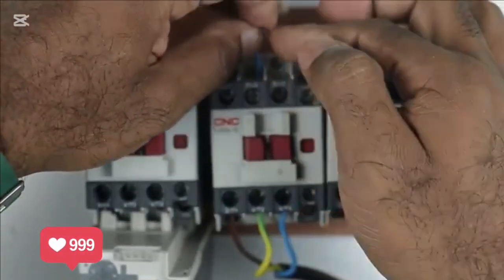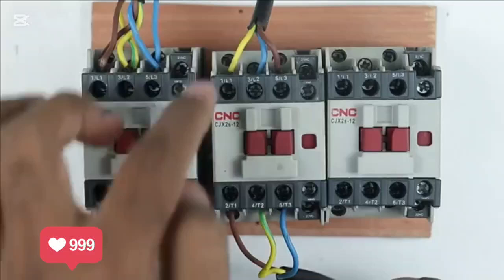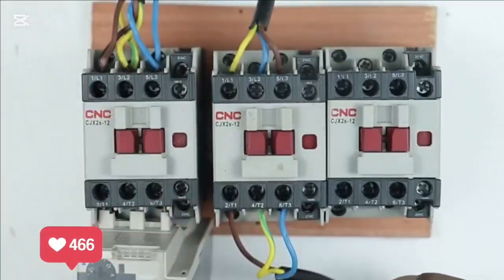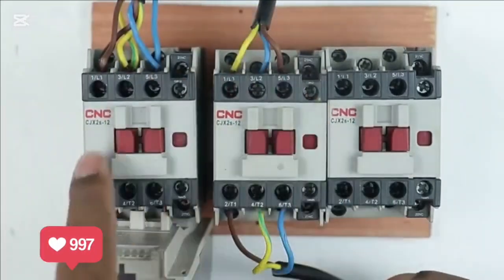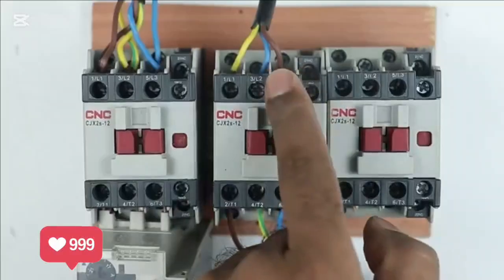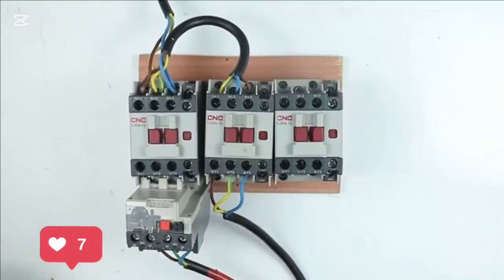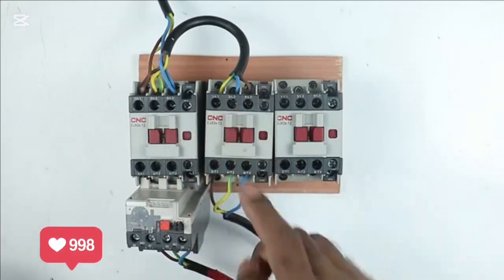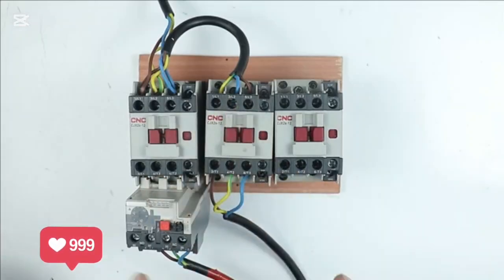With this blue wire here, I am connecting the red wire. You can see here that power supply from red wire will go to this yellow wire and power supply to yellow wire will go through blue wire. And this blue phase wire is connected with red wire. If I do only this much connection, then our motor will run in delta connection because we performed the whole wiring of delta connection.